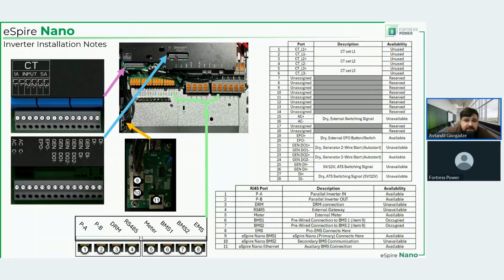Then ports 7 to 14, they are unassigned. Numbers 15 and 16, those are for an external switching signal, right? For some external contactor, you can provide the switching signal, but we're not doing that because that is a feature for Pro EMS, because we have not tested in the standard configuration whether or not it can work reliably. Whereas with the EMS, we have been doing that for years just fine.